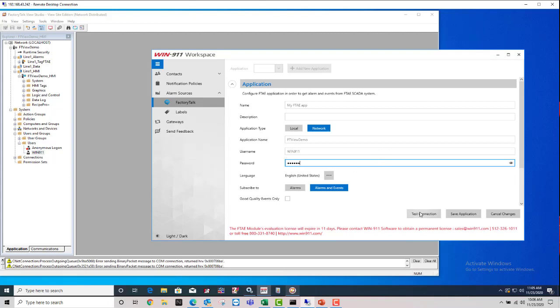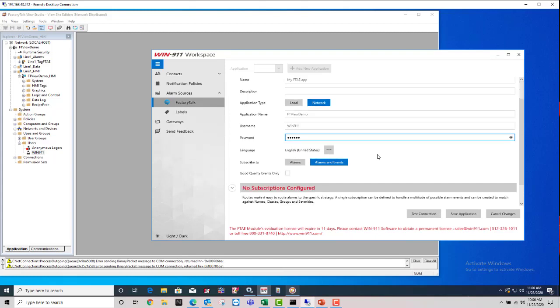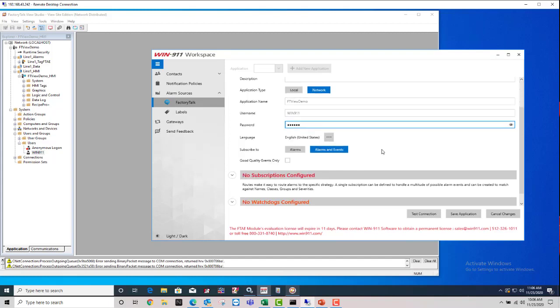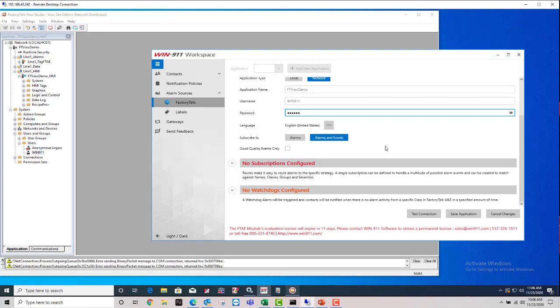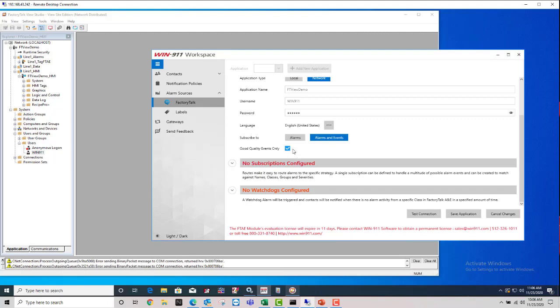So once you're done there, connection is good. And then we get down into what you want to subscribe to, meaning what do you want to see brought into Win911. You can see the option up here in the global settings for just alarms or alarms and events. And checkbox for good quality events only. Check that if you do not want to see any bad or uncertain quality events.